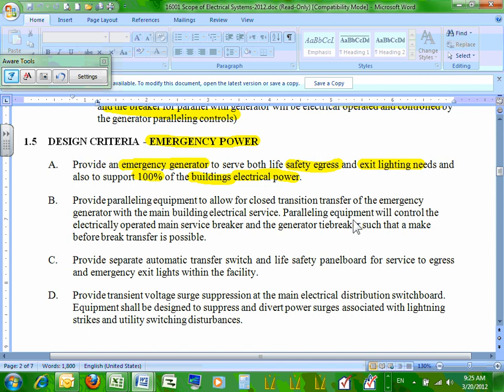These are also draw out breakers. So I got my entire building on generator, but now I've got to deal with my life safety. So what you're probably going to be looking at is, for my genset, here's my code required UL listed for life safety automatic transfer switch that feeds a panel that's dedicated to life safety loads. That's my life safety pathway. And then I have the building switchboard that's supported by the same genset, but that will support the entire loads. So that's what I'm looking for in terms of the emergency power in this section.